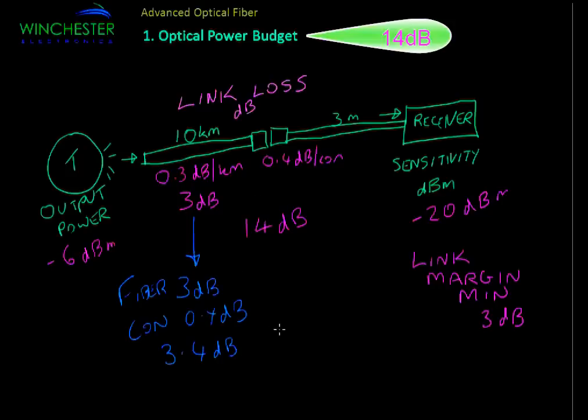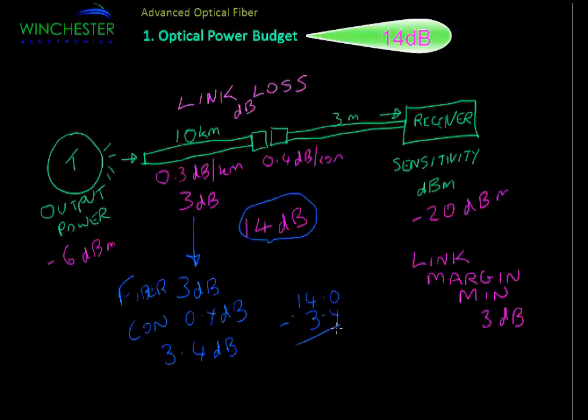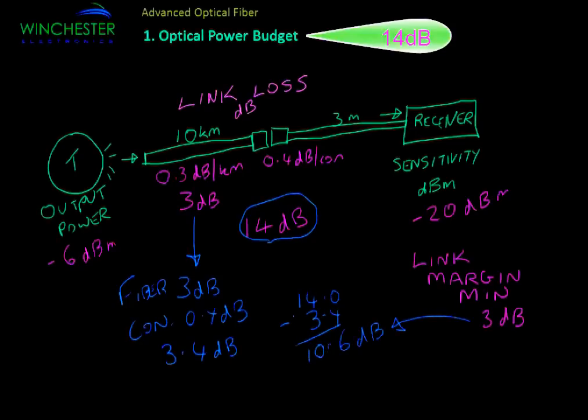Our allowable link loss — the power budget — is 14 dB. So we calculate how much extra we have over and above what we actually need: 14 minus 3.4 equals 10.6 dB. We were looking for a minimum of 3 dB, and we have 10.6 dB, so we have over 10 dB of link margin. This extra margin could be used for installing extra connectors, putting in more fiber, or maintaining it as a safety margin in case connectors get dirty or there's some degradation in the transmitters or receivers.